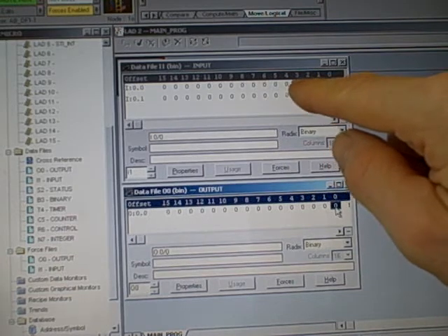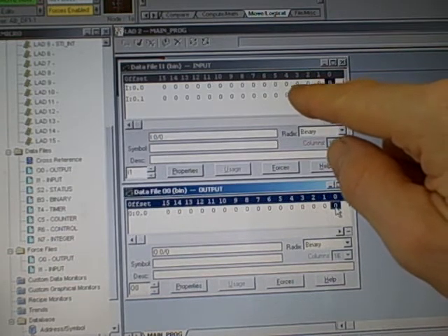So what the PLC does as it executes its program is it goes through and scans all the input channels and updates these input bits according to the electrical status that it sees at the wired input channels. Then it executes the program itself. In this case, as I said, there is no ladder logic program. We can see that there's really only 1 rung in the program, and it terminates in an end instruction. So there is no logic programmed into this PLC at this moment.